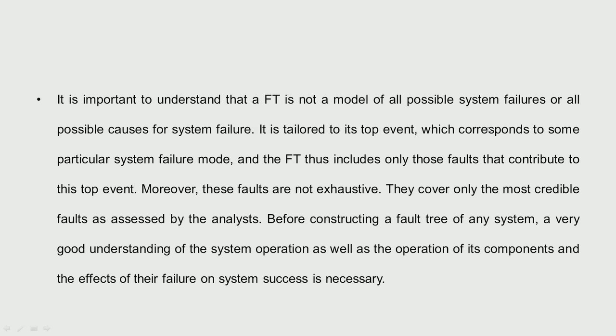One thing we should keep in mind: a fault tree is not a model for all possible system failures — it is tailored to the top event. You postulate an event and find out in what way it can happen. So it very much depends on your ingenuity in how you postulate. It is a very, very extensive list, so you need to have knowledge of the plant, knowledge of the experience which other plants have had, and also what sort of failures can take place. We are talking about credible faults most likely to happen, so we need a very good understanding of the system, its operation, and also the operation of the components.